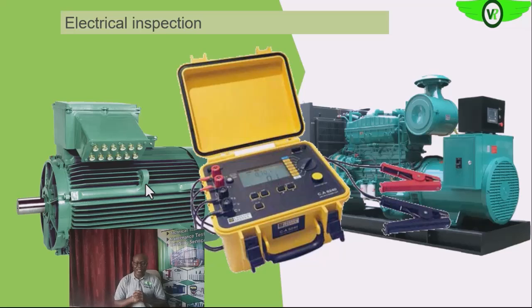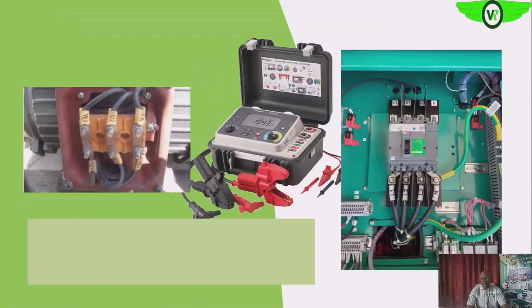So the next section of tests that we are going to be looking at for the electric motor and the generator is the electrical inspection, or the other part of it, which is the electrical test. The major tests in this section are the insulation resistance test, the dielectric withstand test, and the resistance test, that is checking the resistances of the windings. And also we are going to be looking at the power factor, or tan delta, or dissipation factor test.